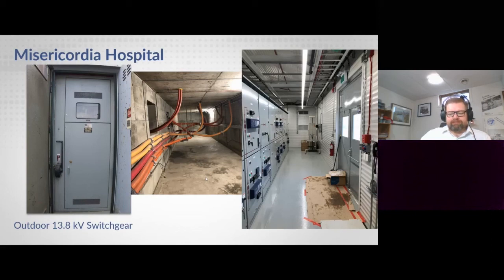So I mentioned earlier the hospital example. What we're looking at here is some 50 to 60-year-old outdoor rated gear on the far left. Yes, this is outdoor rated gear, there's an outside door that's open. There's the switchgear inside, a big fuse disconnect, and the relaying's on the opposite side of the system with the contactor. In the middle are the cables.